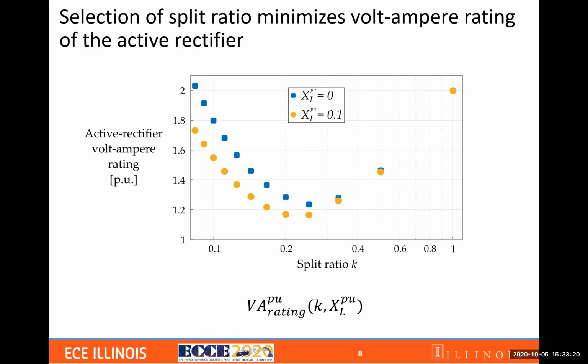And you see here when we change the XLPU, for example, from 0 to 0.1, then the active rectifier is going to change as well. And it turns out XLPU is the only parameter that sets the active rectifier volt ampere rating. So because of that, for each generator there is a single value for XLPU, and for that XLPU, the power converter is tailored for that particular XLPU quantity.